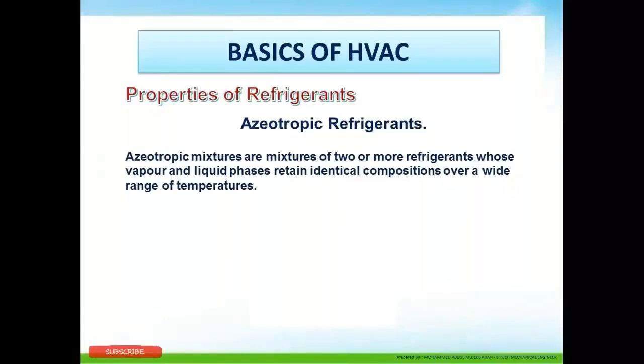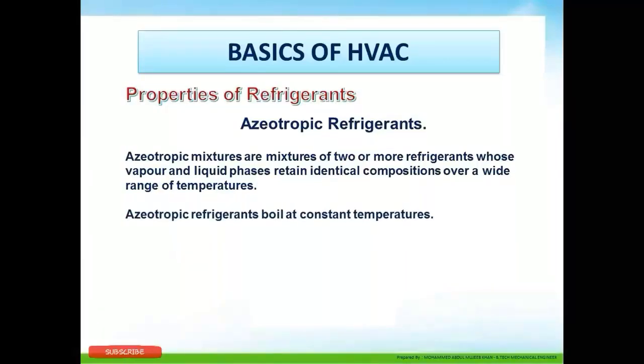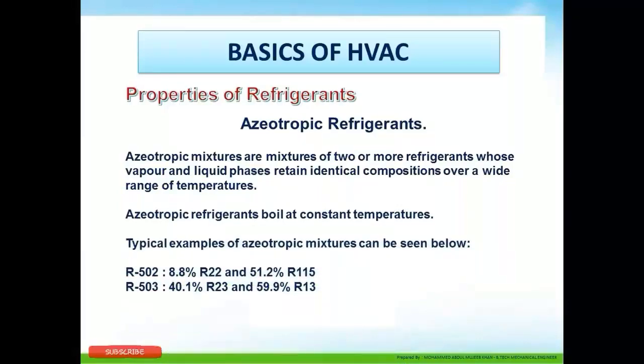An azeotropic refrigerant is a mixture of two or more refrigerants whose vapor and liquid phases retain identical composition over a wide range of temperatures. A liquid refrigerant can be in its pure state or a mixture of two or more refrigerants. To be azeotropic, it needs to retain that identical liquid-phase composition over a wide range of temperatures. Azeotropic refrigerants boil at a constant temperature. Typical examples are R502 and R503.